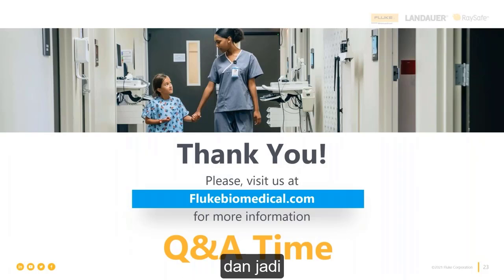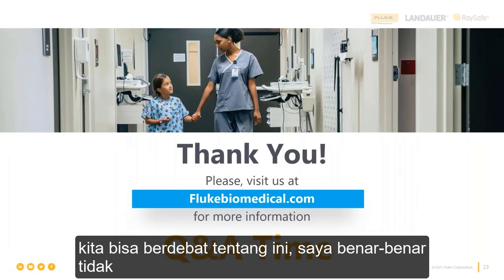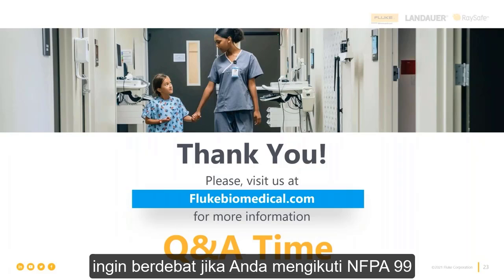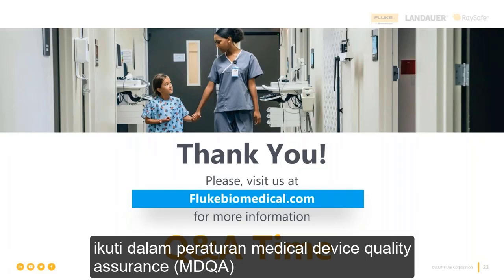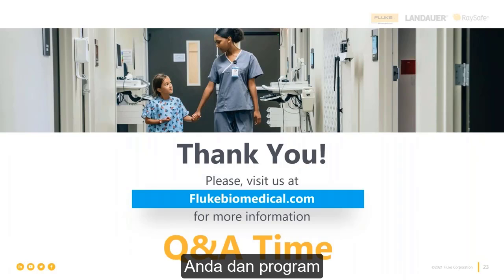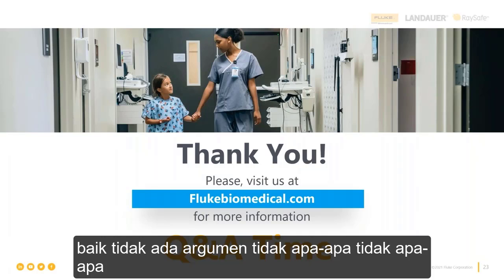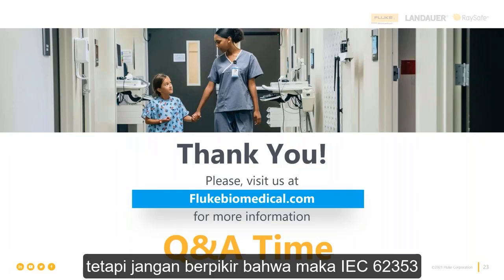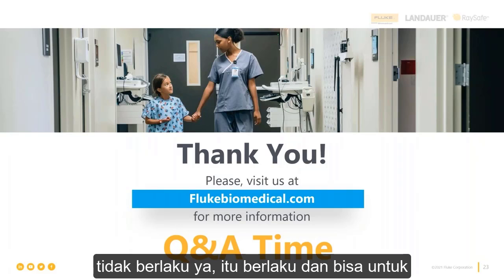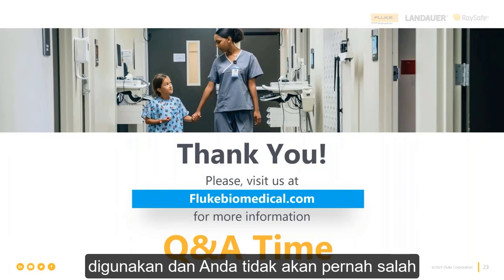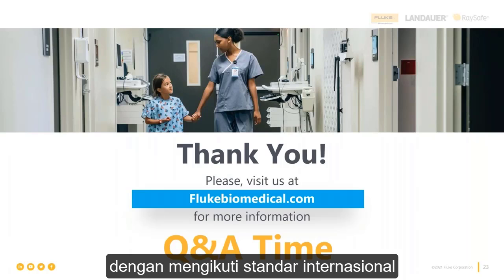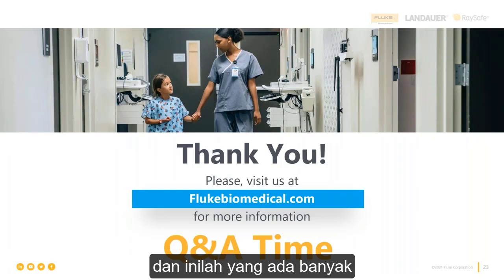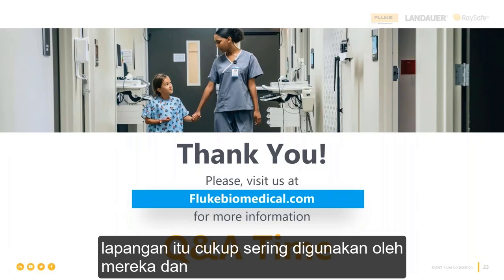And so, we can argue about this. I really don't want to argue. If you're following NFPA 99 and that's what you said you're going to do in your medical device quality assurance policy and program, fine. No argument. It's okay. But don't think that IEC 62353 therefore does not apply. It does. It's available to be used, and you'll never be wrong by following the international standard. And it is used. A lot of our manufacturers and OEM service are doing that 62353 at the hospital level in the field. It's used quite often by them.